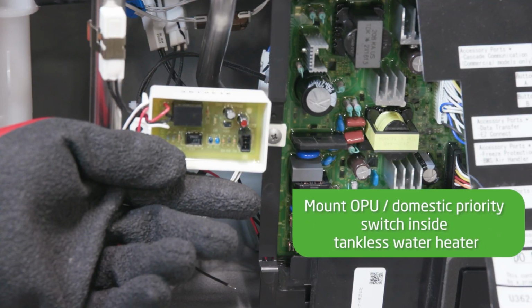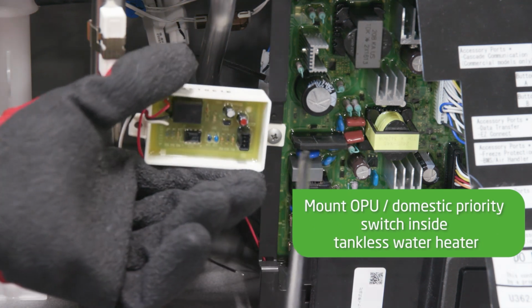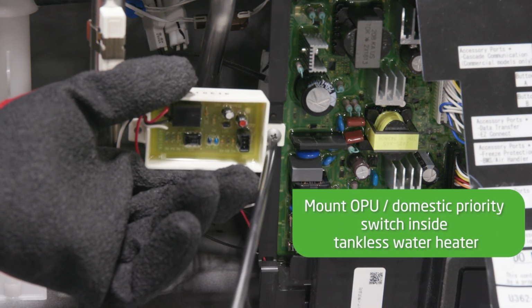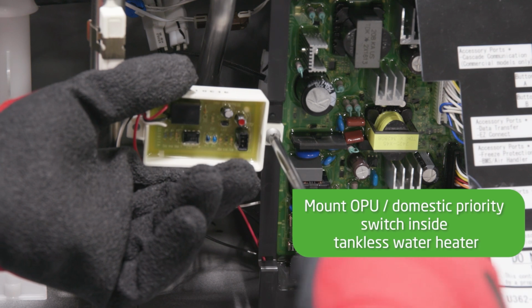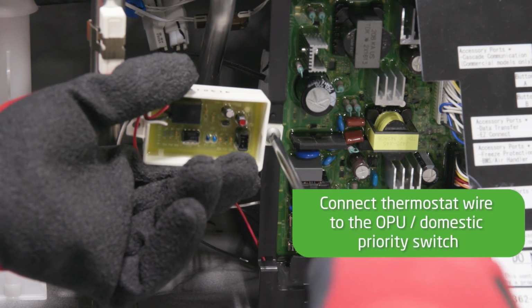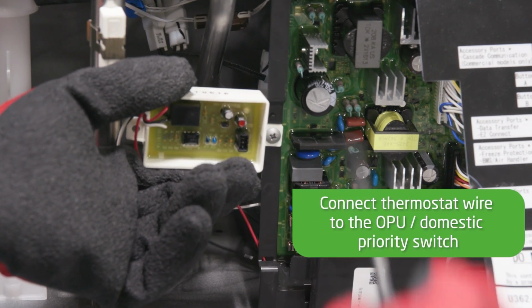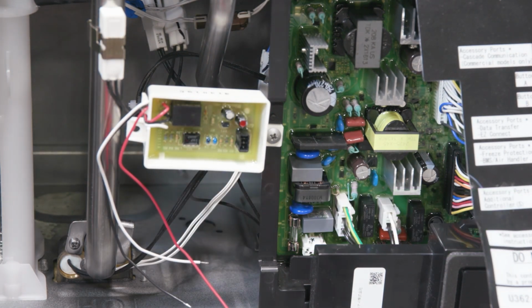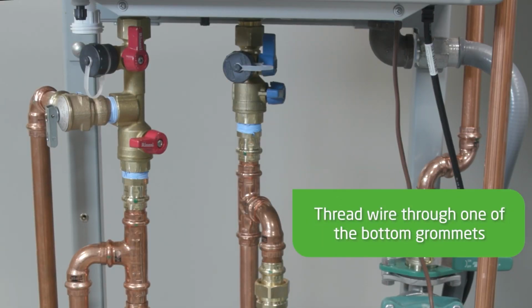Remove the cover of the tankless water heater and mount the OPU domestic priority switch inside. Connect general purpose thermostat wire to the OPU or domestic priority switch. Thread the wire through one of the bottom grommets and reattach the tankless water heater cover.